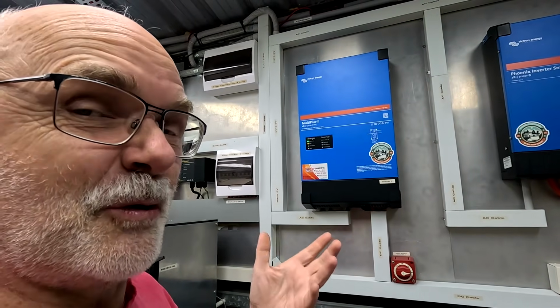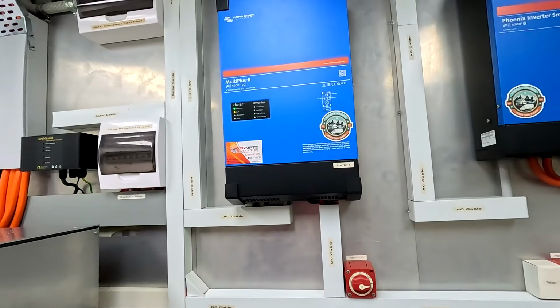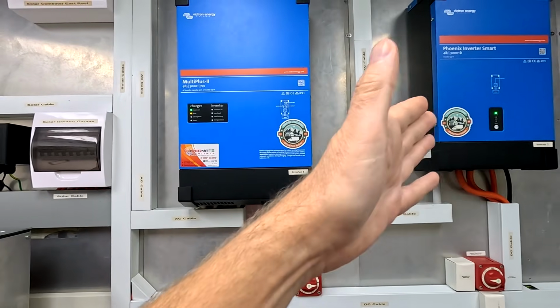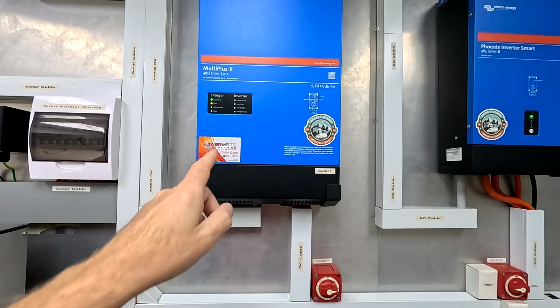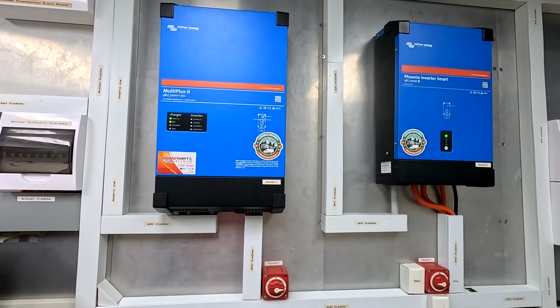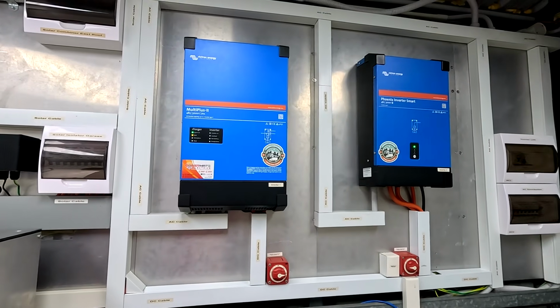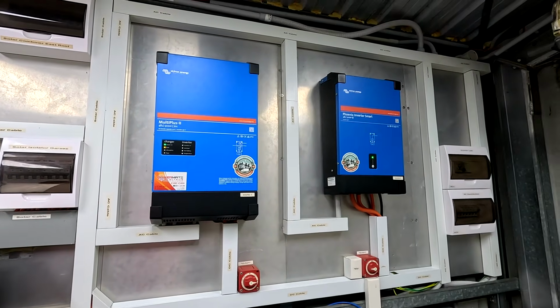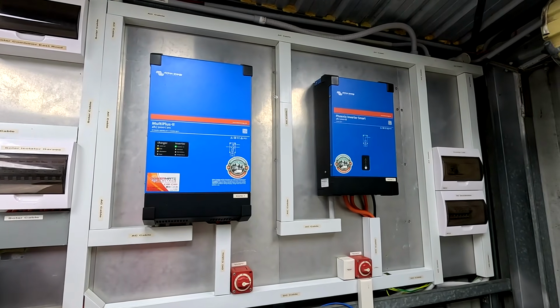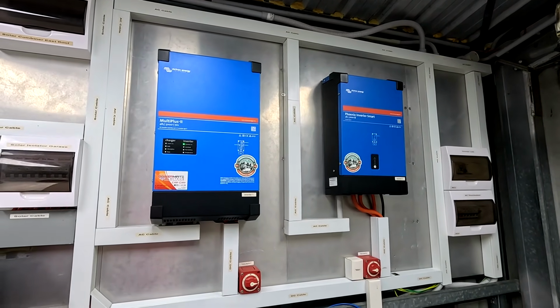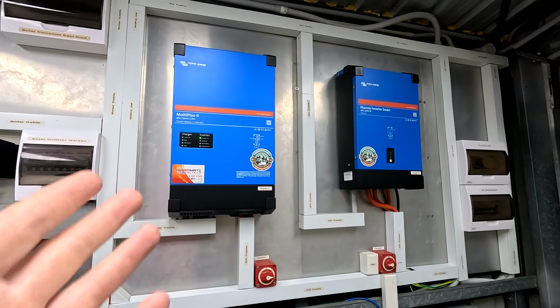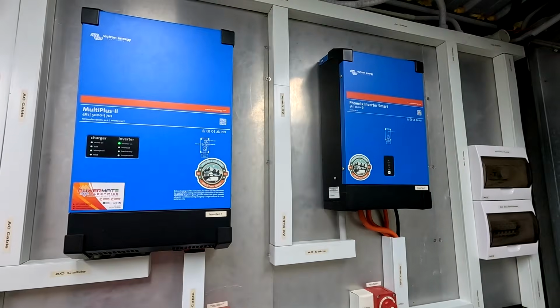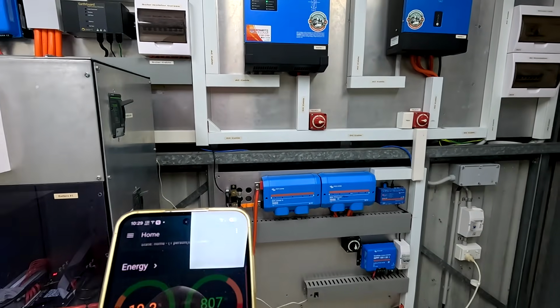Technically it's not a problem. We are wasting a tiny bit of energy now, of course, because of the efficiency, DC, AC, AC, DC again. But the multi-plus will turn off the inverter now in a second. And let's see if we see a flicker. No flicker at all. Lights stay on. You could hear the click inside the multi-plus, and the Phoenix is off again until we have the next peak load.